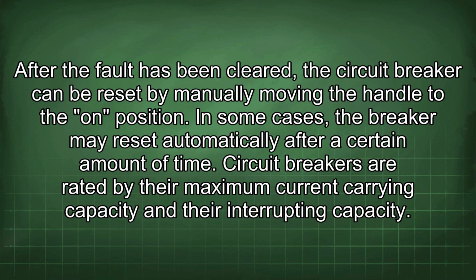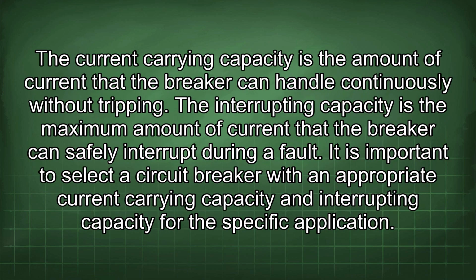After the fault has been cleared, the circuit breaker can be reset by manually moving the handle to the on position. In some cases, the breaker may reset automatically after a certain amount of time. Circuit breakers are rated by their maximum current carrying capacity and their interrupting capacity. The current carrying capacity is the amount of current that the breaker can handle continuously without tripping. The interrupting capacity is the maximum amount of current that the breaker can safely interrupt during a fault.